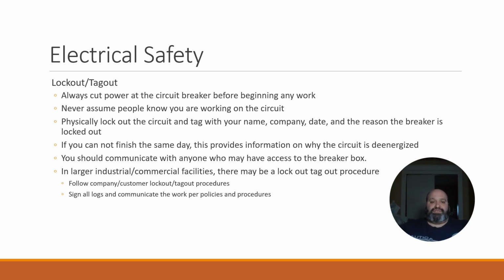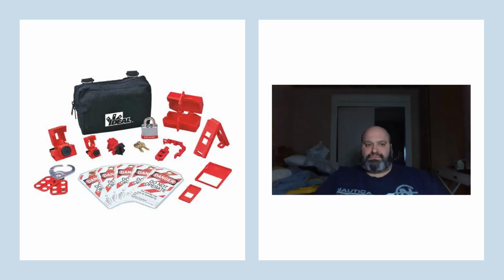In larger industrial and commercial facilities, there may be a specific lockout tagout procedure — just make sure you're following company policy. For those working on commercial kitchen equipment, you'd frequently want to talk to the site manager — the grocery store, restaurant, or retail store — and make sure you're following their lockout tagout procedure, signing all logs, and communicating the work per procedure. This isn't every lockout tagout kit, as there are different types of components, but this is basically everything that's going to be in most lockout tagout kits, for your standard breaker.